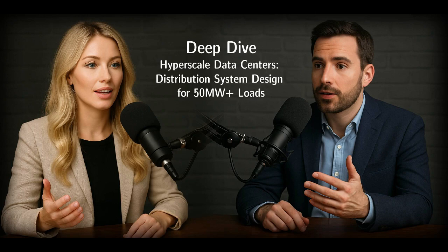Got it. So how does one single 50 megawatt data center stack up against that picture? What does it actually do to the grid? Well, the contrast is pretty stark. First, the load size. One 50 megawatt data center, that's like taking 3 or maybe even 4 entire traditional distribution feeders and giving them to one customer. Wow, 3 or 4 feeders worth. Yeah. Second, the load factor. We talked about 60 to 70% for traditional feeders. Data centers are often running at 95%. Continuous, almost no break. 95%.